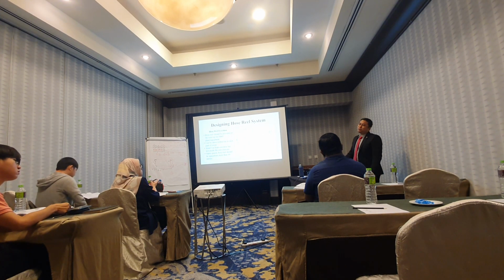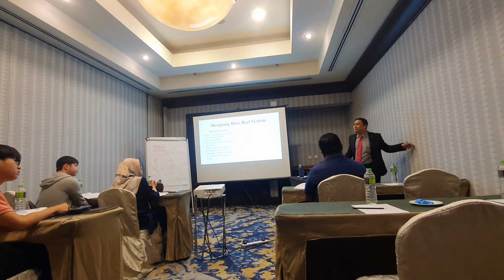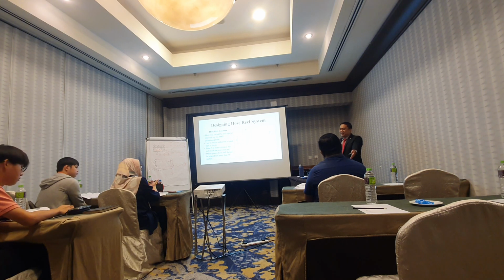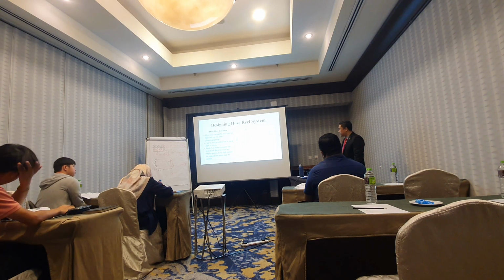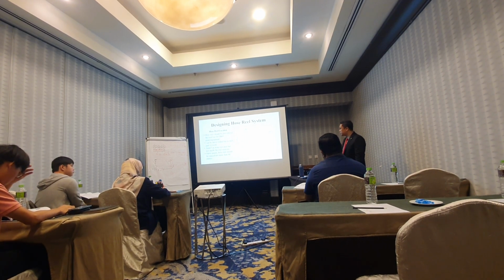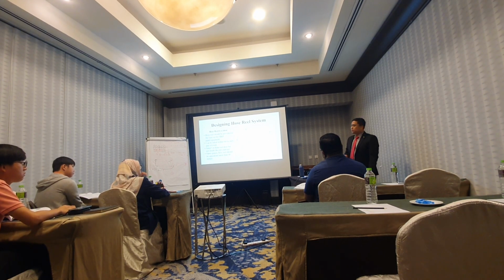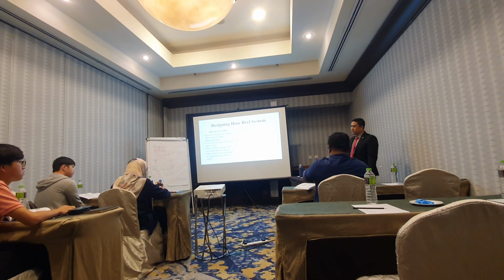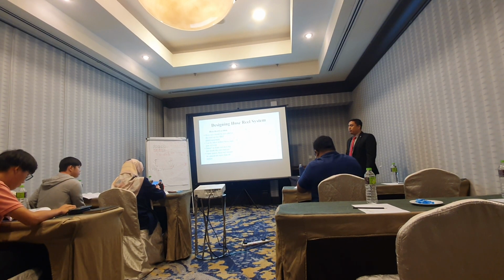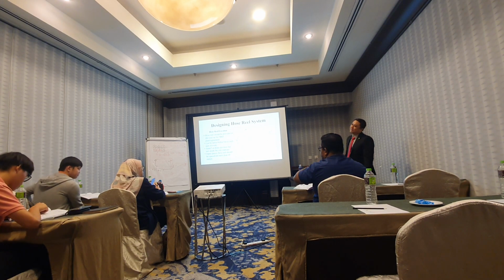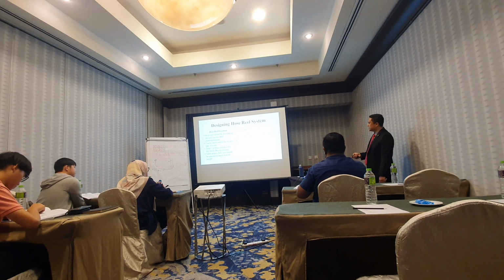But whenever you are the designer, kadang-kadang you tak ada pun party wall ni, belum ada lagi. So how can you design? There are syarat yang bomba dah tetapkan, there are regulations yang bomba dah tetapkan. You can make the hose reel punya jarak tu 2/3 of this 48. So it is 32. Bukan 30 lah, 32 boleh lebih 2 meter. 2/3 of 48 is 32. Betul. So that is where you can use it lah.